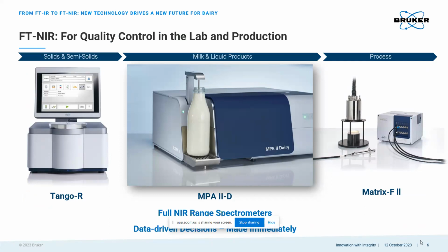Whereas dispersive NIR systems are used for inline analysis. And Bruker, on the other hand, offers FT-NIR technology for both benchtop and inline analysis. And all of these systems are full NIR range spectrometers, utilizing 4,000 to 12,500 wave numbers. And since they're all based on the same FT-NIR platform, users can choose the right analyzer for any job without having to compromise on precision and accuracy.